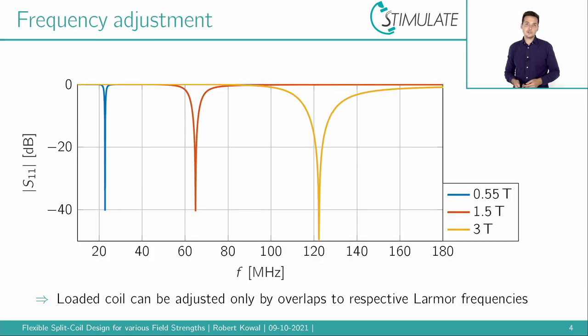The next step, the split coil model was loaded with a phantom and adjusted at different field strengths solely by changing the overlapping angle. For the exact values and other parameters, I would like to refer to our abstract. A successful adjustment is here now visualized by the reflection coefficient S11 for the 0.55, the 1.5 and the 3 Tesla coil.